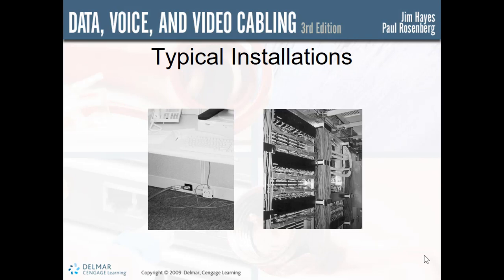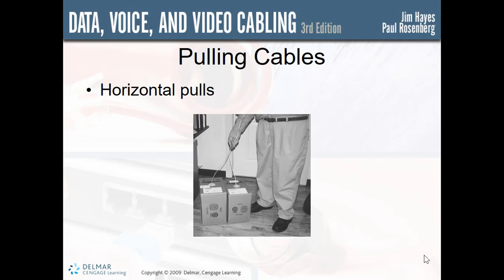Some applications will have cables in conduit to protect cables in areas where damage may be possible, to prevent EMI where that might be the problem, or to assist in fire stopping. Remember, any cable that goes through a floor has to have fire stop put onto it to stop the hole, to keep fire from going from floor to floor.